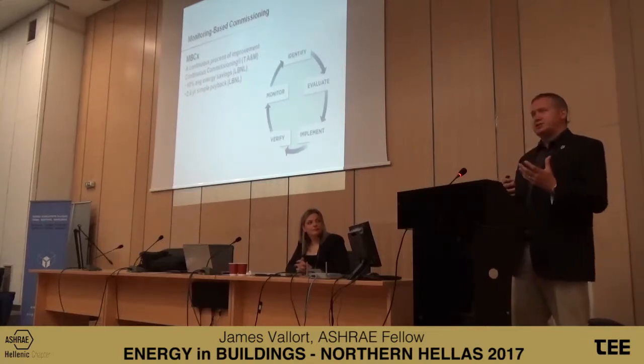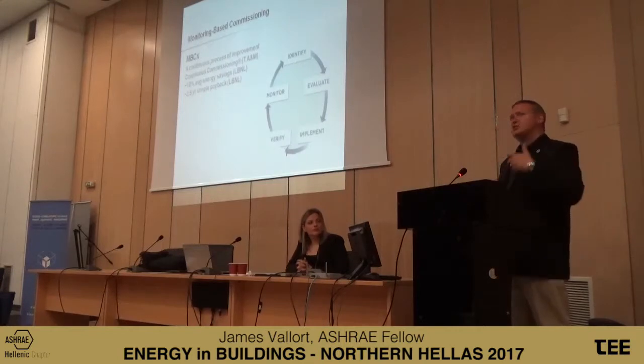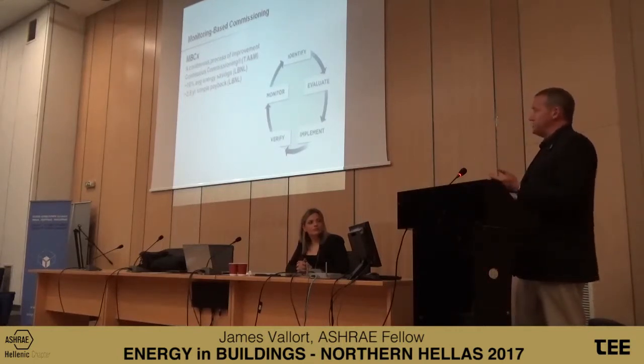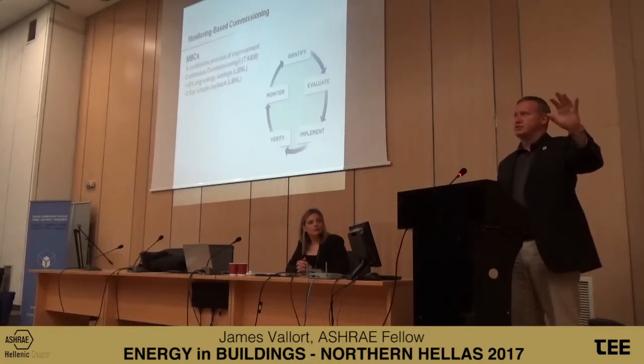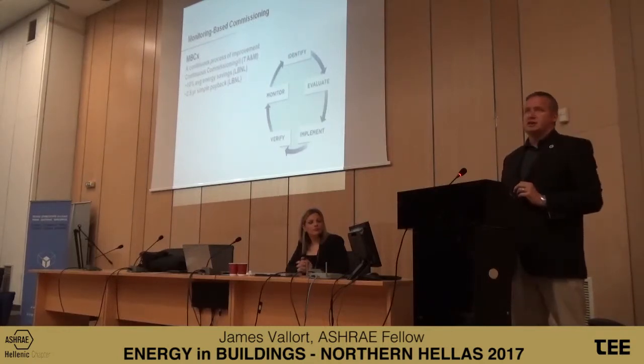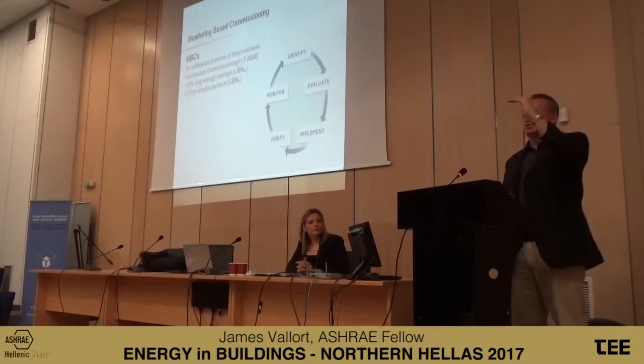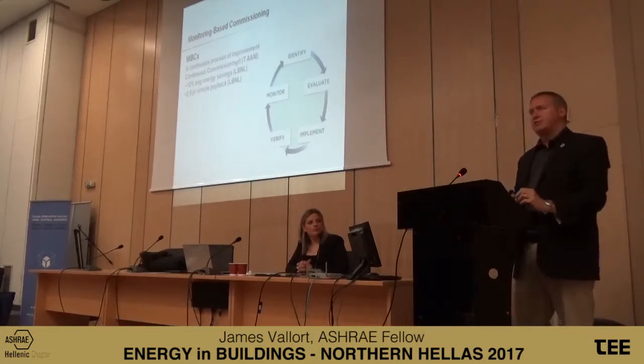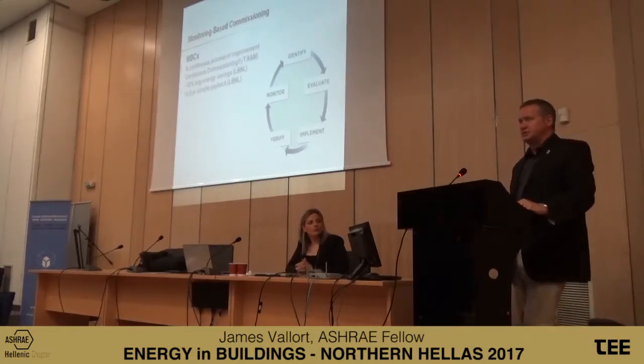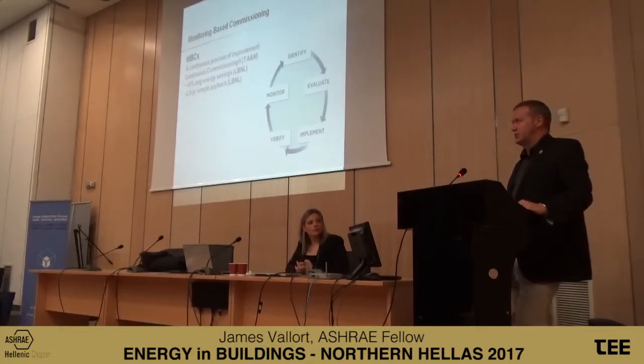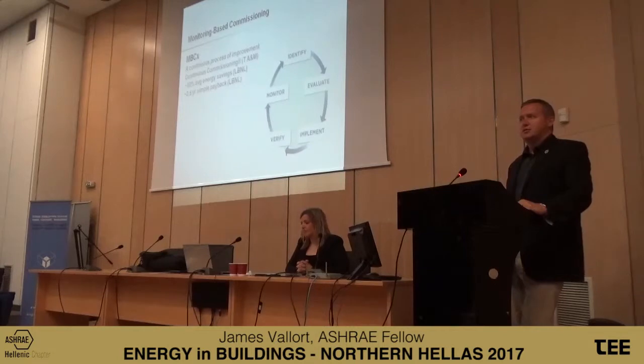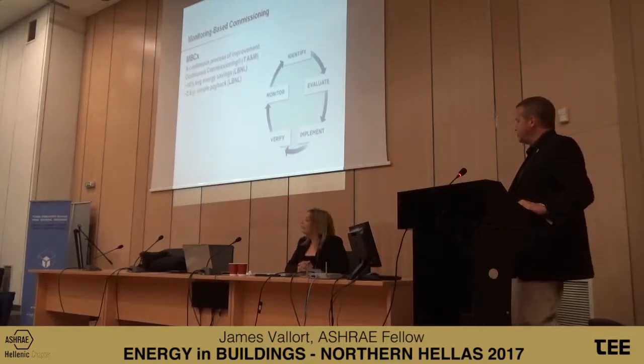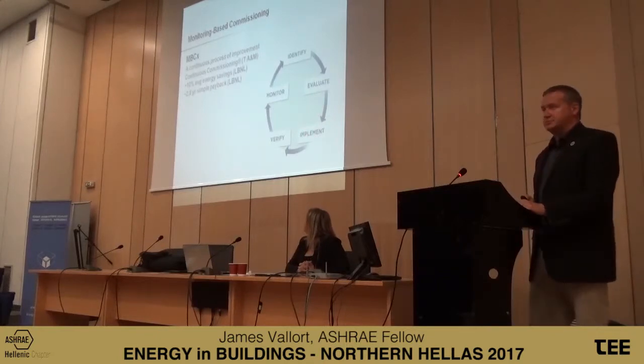With fault-based detection and monitoring-based commissioning, you continuously monitor your system and identify something that just doesn't seem right. Let's have an engineer take a look at that instead of going through all 10,000 points - by the time they finish, they're already late getting back to the first one. So we allow you to focus the effort of your staff, because as owners put in more automation, unfortunately they're also cutting physical manpower. We need to make that manpower more efficient since there's usually less of it than before. This allows you to identify, evaluate, and implement.